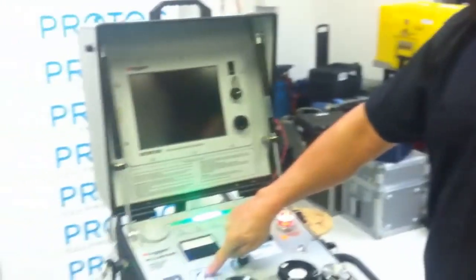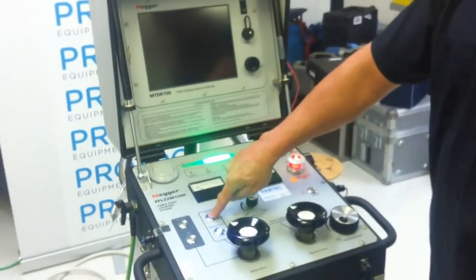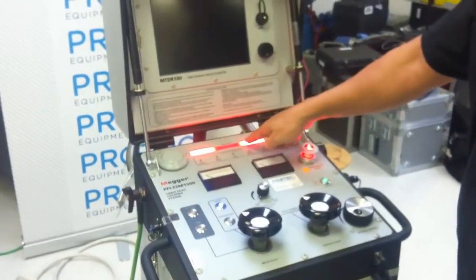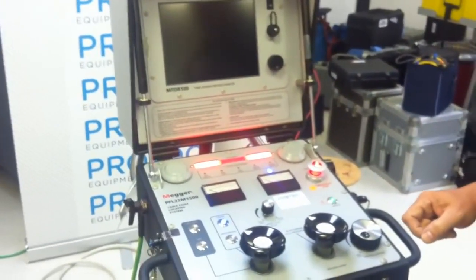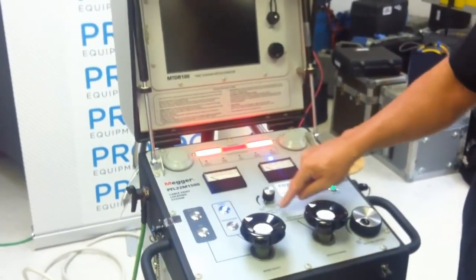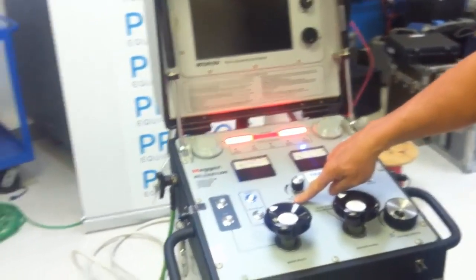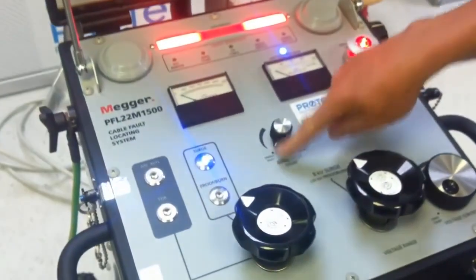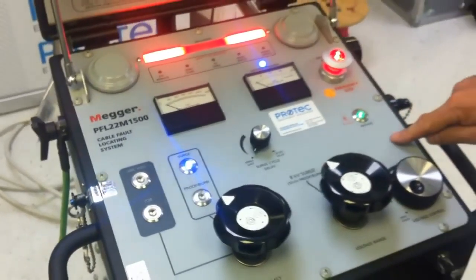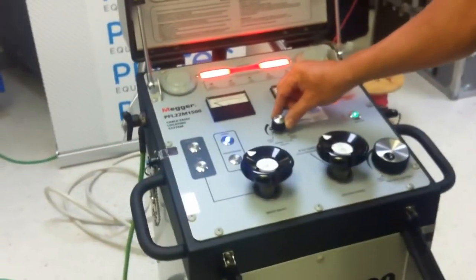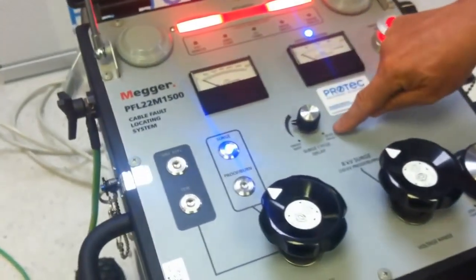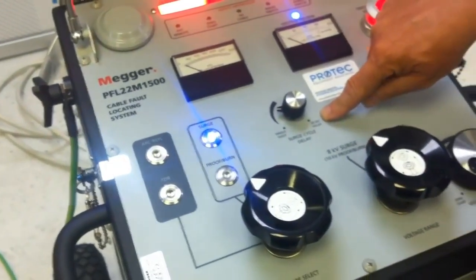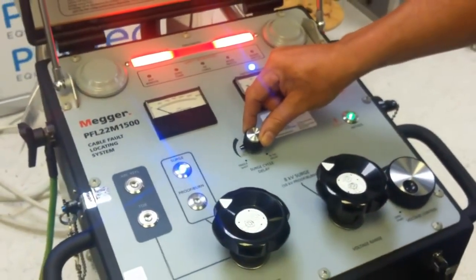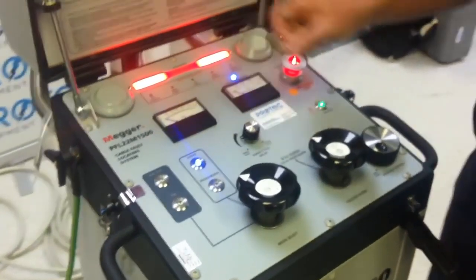If I want to now implement a direct thump or a thump test on the cable, I merely select surge, and the system goes to an ungrounded state. I can adjust my cycle either for a single shot where the instrument will not discharge until I press the initiate button, or I can set it for a time sequence up to 30-second delay. I'm going to go ahead and just set it for a nominal time sequence.